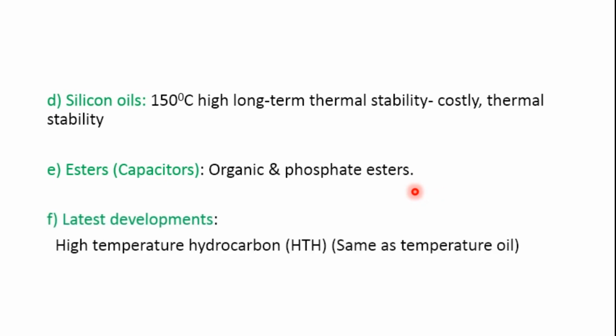Organic esters have a high boiling point in relation to their viscosity and therefore have high fire points. They have a good viscosity-temperature relationship and are extensively used in capacitors. Phosphate esters have a high boiling point and low inflammability, and therefore they are used in transformers installed in hazardous areas. Nowadays we also have the latest developments.